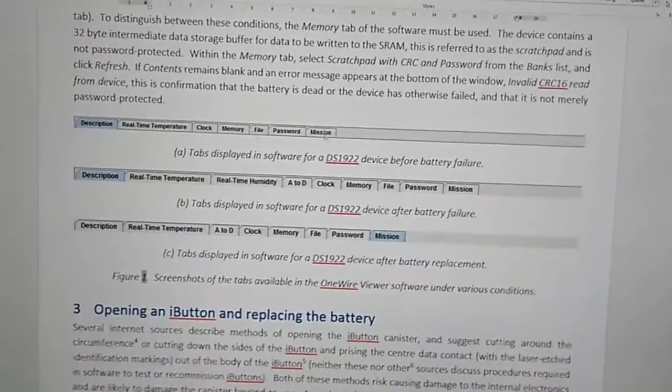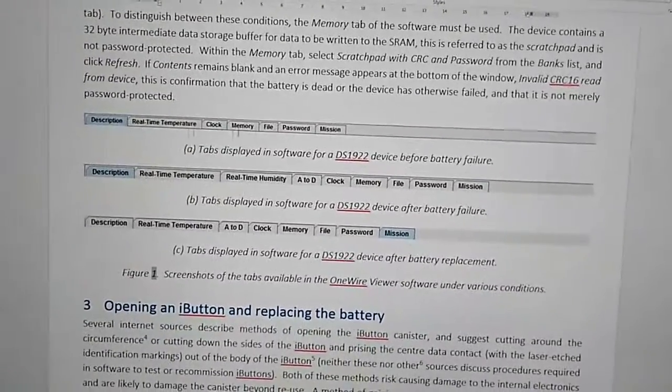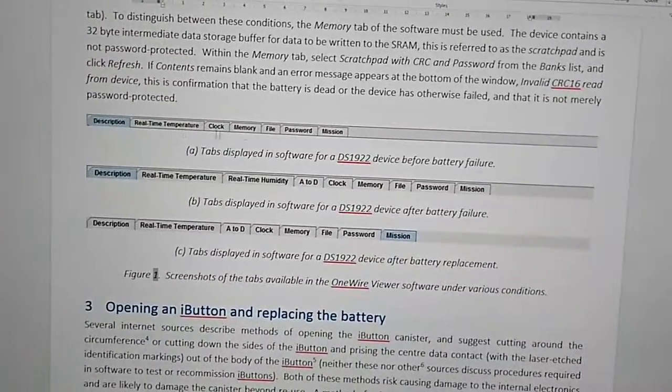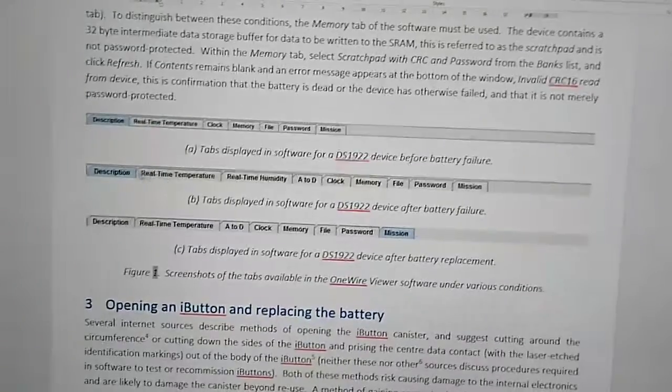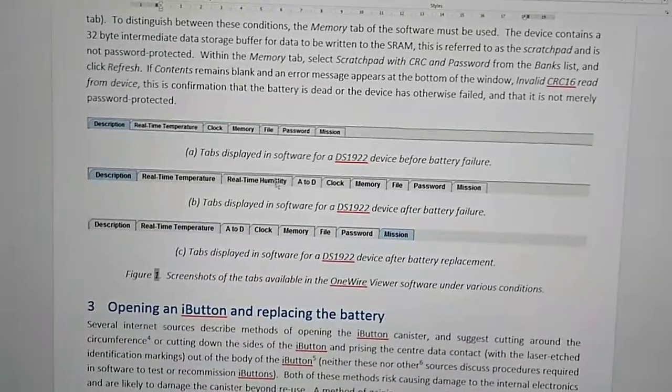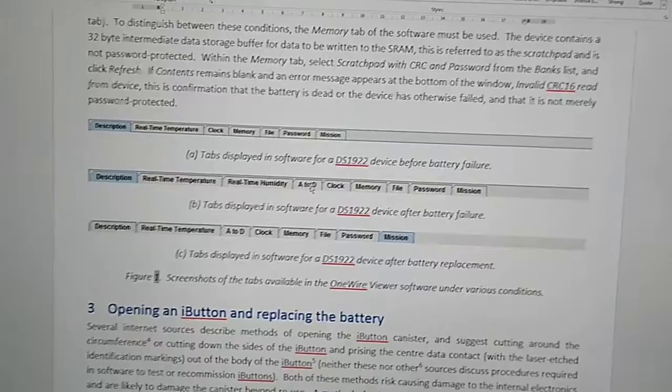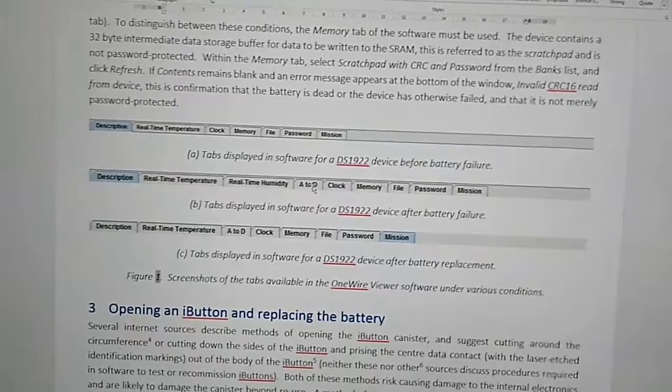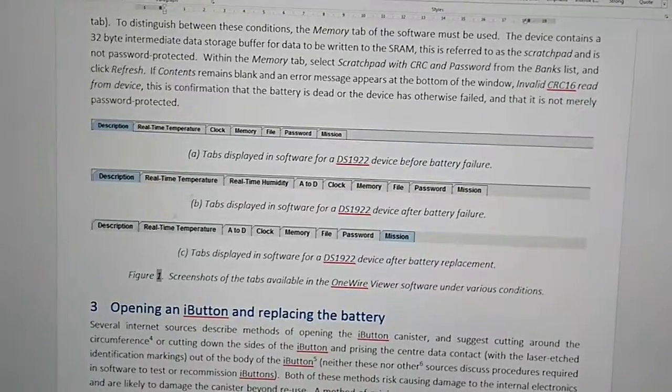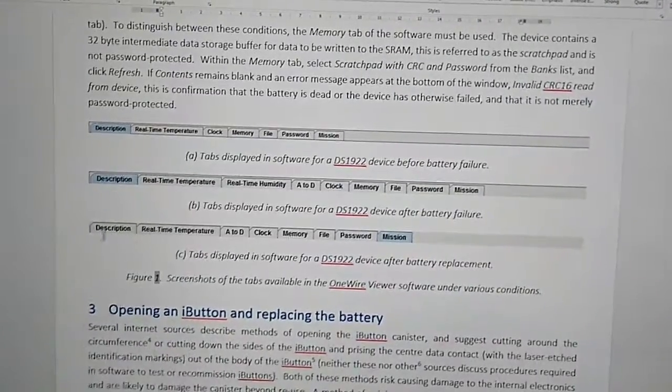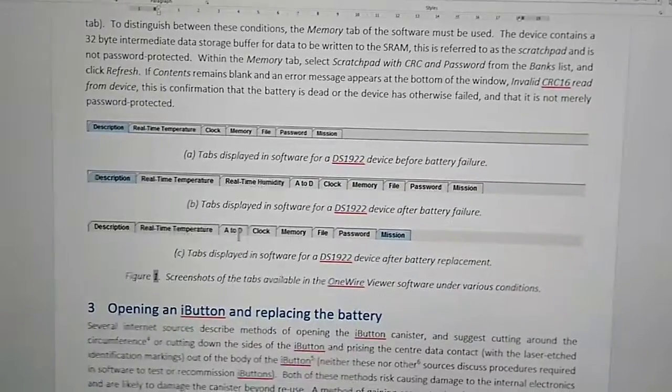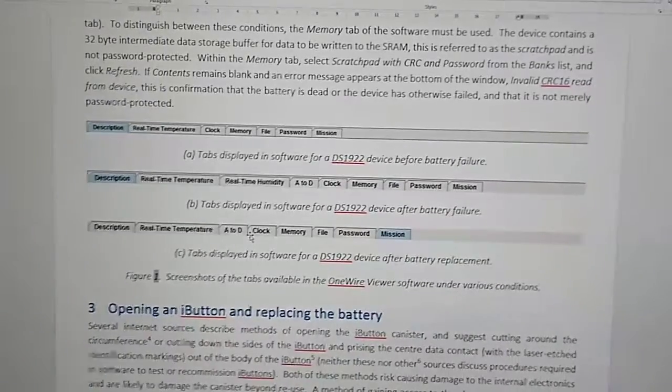So in a functioning iButton Thermochron, you get these tabs. If the battery's failed, you get these extra real time humidity and A to D tabs. And after you've replaced the battery, you then don't get the real time humidity tab, but you still get the A to D tab.